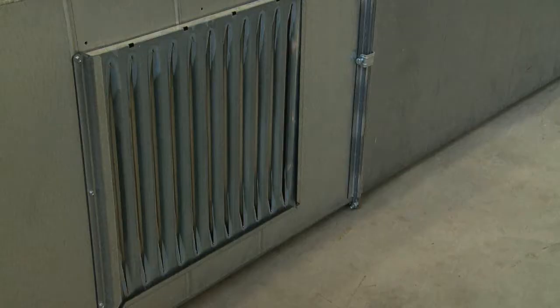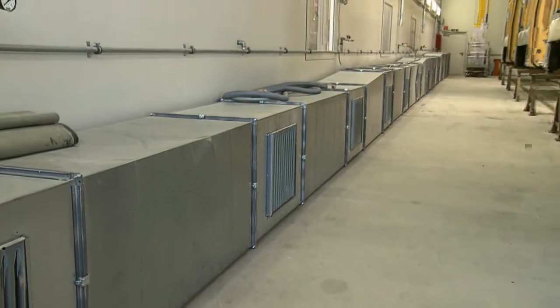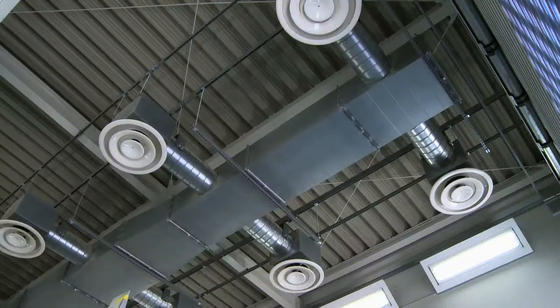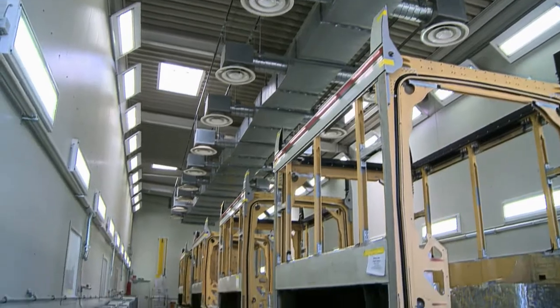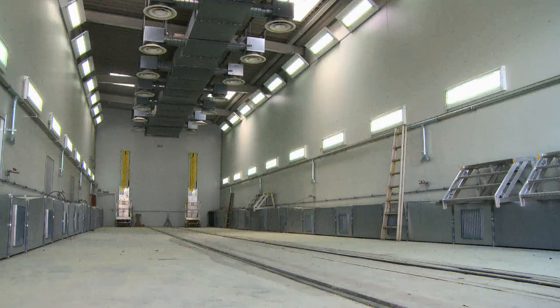The sanding tools can be docked at 10 connection points. The extraction system in the left and right side walls provides for the extraction of air and particles using integrated filters. Amply dimensioned lighting fixtures mounted on the ceiling and walls uniformly illuminate the work area at more than 900 lux.